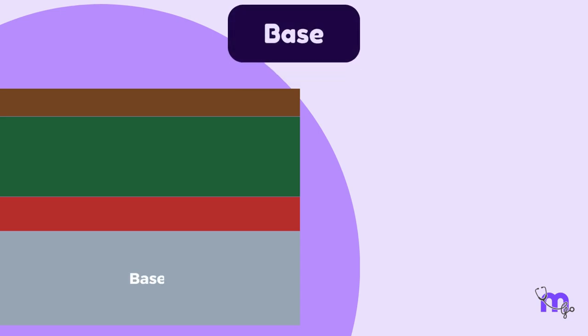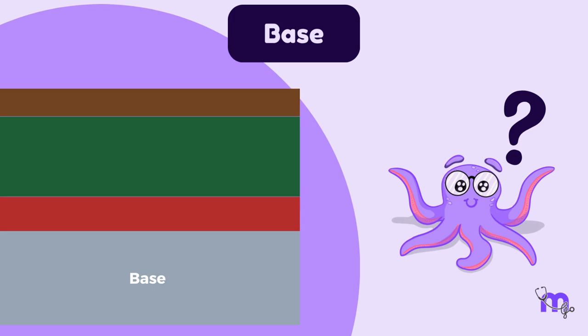Let us look at the composition of the intensifying screens. It consists of a base, reflecting layer, phosphor layer and a coat. Let us learn about the role of each layer. The first one is the base. This is made of polyester plastic material, about 0.25 mm thick. Why do you think this layer is important? Well, it's because all the other layers depend on it for mechanical support.